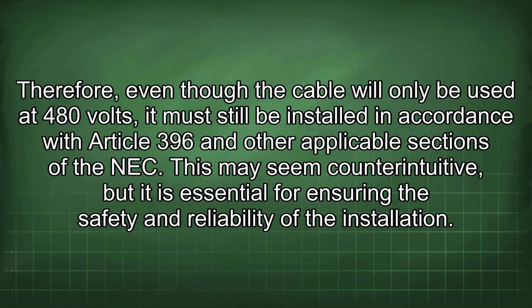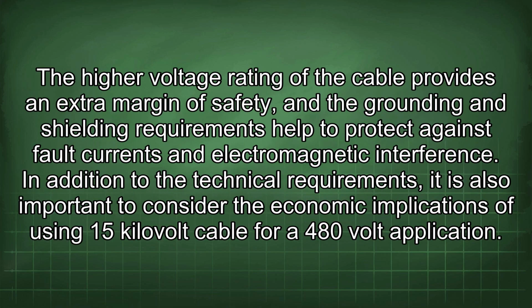This may seem counterintuitive, but it is essential for ensuring the safety and reliability of the installation. The higher voltage rating of the cable provides an extra margin of safety, and the grounding and shielding requirements help to protect against fault currents and electromagnetic interference.